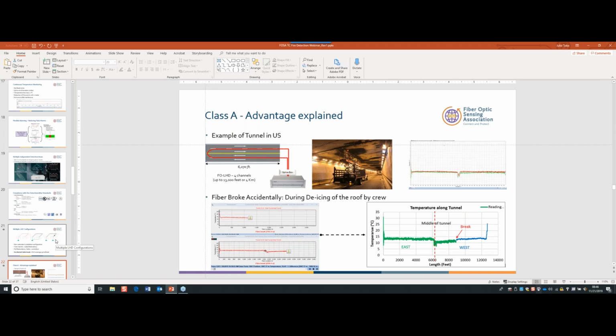And following up on the break question, I had a question about how easy is it to replace damaged cable, and also related to that, a question about the ability to do testing or inspection, which is basically trying to activate the system to make sure that it's still functioning. Yeah, very good question. Because we're a temperature sensing system, every year in every installation we've done, you can come in and monitor the temperature. It's quite important, and the accuracy of the temperature can be tested not even within the rooms you want to protect, but in different areas within the sensing cable system.